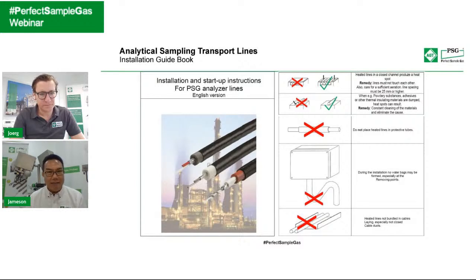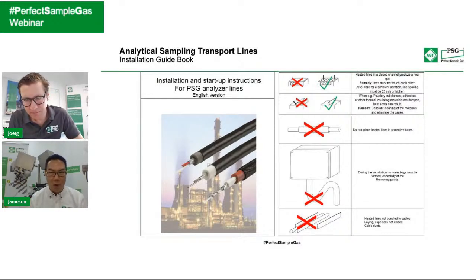please ask for the installation handbook from the supplier, and make sure that the contractor doing the installation reads the installation guidebook. This is very important. When they run the cable tray, they must not lay the lines side by side. There should be spacing, or even if they cover the cable tray, make sure the top has holes so that the ventilation is enough to dissipate the heat. They should not double insulate the heated line, and they should not have any water collecting point like this.